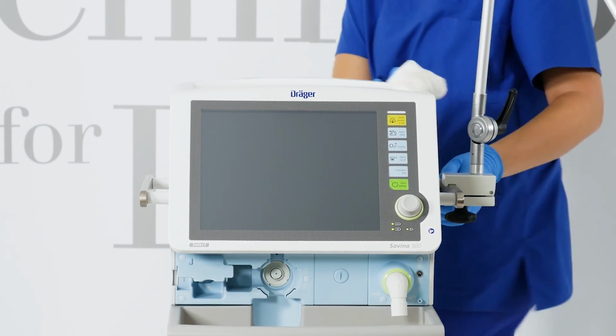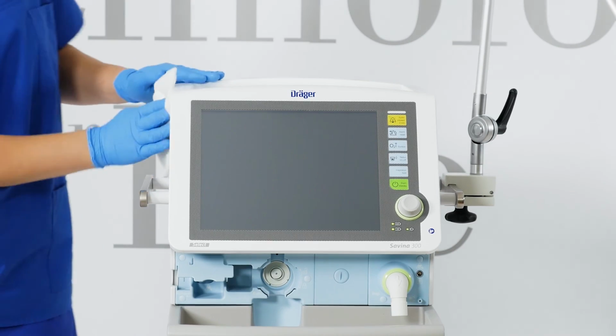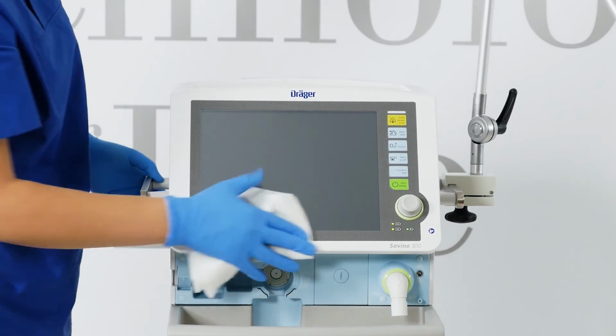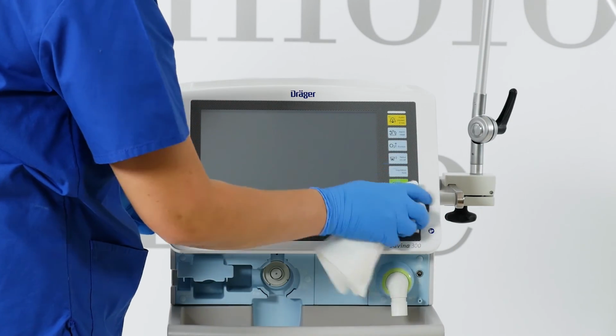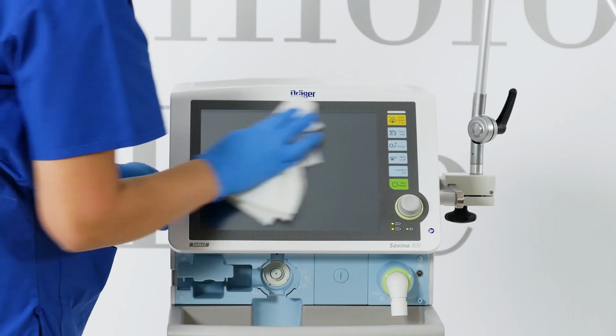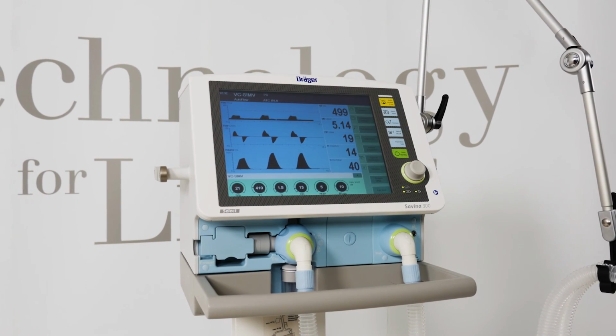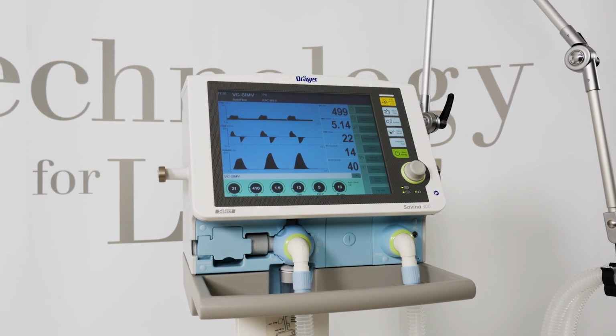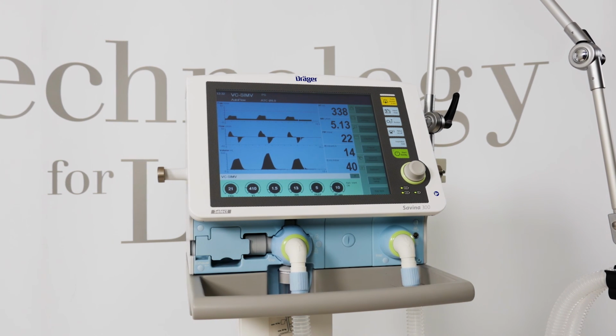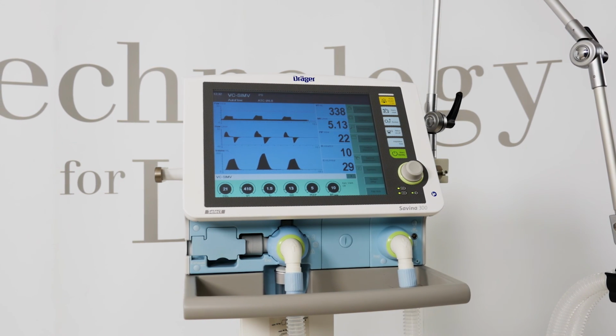Make sure that only cleaned and disinfected reusable components are sterilized. The hot steam sterilization can be performed at 134 degrees Celsius. Observe instructions for use of the device. To ensure the effectiveness of sterilization, a minimum sterilization time of 5 minutes is required.